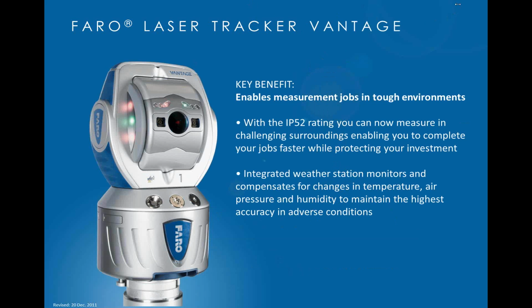So some of the key benefits on the laser tracker. Then we have the IP52 rating, which allows us to measure in very harsh conditions. We can actually have very dusty environments or very damp and moist environments as well, and we can measure jobs very easily within those environments using the IP rating. But also, as with the previous laser tracker, we have the integrated weather station on the system, so the tracker is constantly monitoring temperature and pressure and humidity, and it optimizes itself to compensate and cope with the changes in the environment.